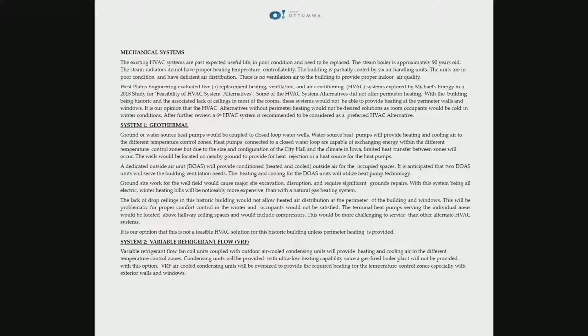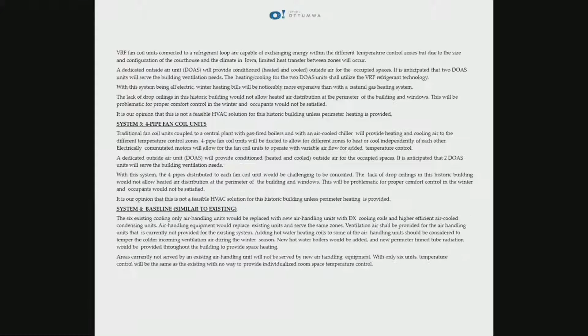Variable flow, system two, is very energy efficient but doesn't utilize natural gas, which is cost-favorable in this town. The first two systems use all electric. Variable flow is again a very diverse system, but it doesn't get heat to the perimeter of the building. The four-pipe fan coil system can use natural gas for heating and hot water, but it still doesn't provide heating at the perimeter walls.